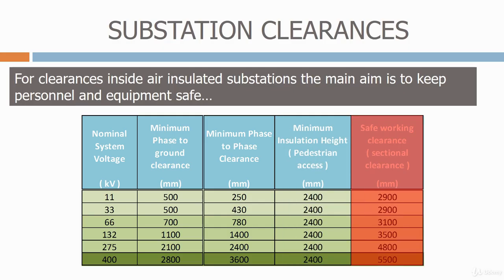In the final column, we have the safe working clearance, sometimes called the sectional clearance. This is used to define safe working distances to the work areas that we need inside the substation to do maintenance on equipment. Let's now see how all these safety clearances are used to design an air-insulated substation.